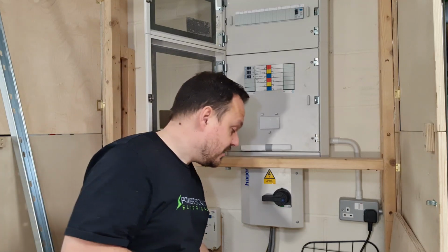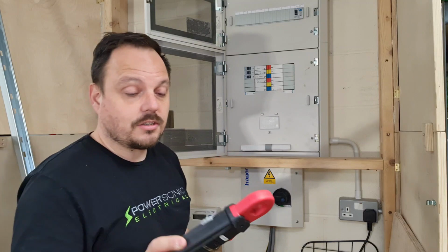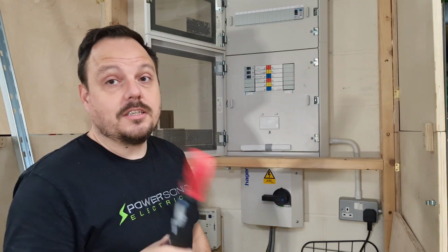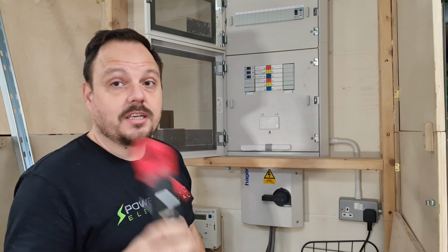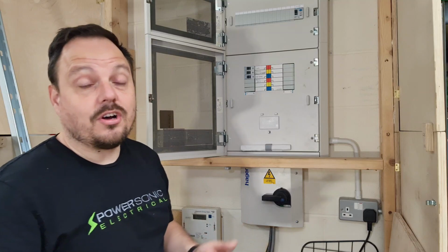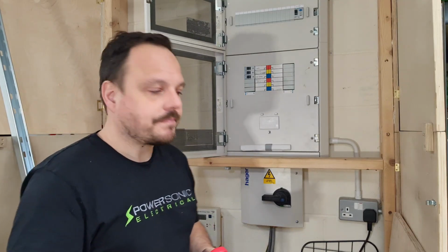So this new TIS meter, I'm going to play around with this quite a lot more now on most of the installs we're going to. I'm going to be checking what sort of values we're seeing for typical DC circulating currents, and I'm also going to be checking the AC leakage as well on installs. Measured it here today and there's basically none, unless I've got the computers turned on. As you'd expect, they naturally leak a little bit.